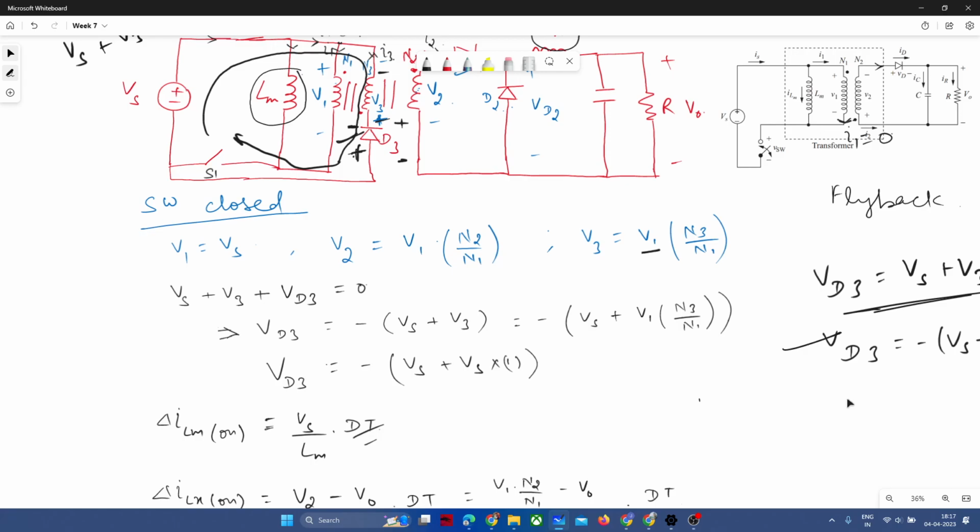Generally, we use silicon steel. In silicon steel, it is limited to 1.8, 1.9 Tesla. Yes, if you add a cobalt kind of alloy, that is also limited, and however the cost will rise like anything. But after adding cobalt, some material named Vacoflux or Vacodur, if you search in Google after this session, you will be able to observe that its magnetic flux density is up to 2.3, 2.4 Tesla.